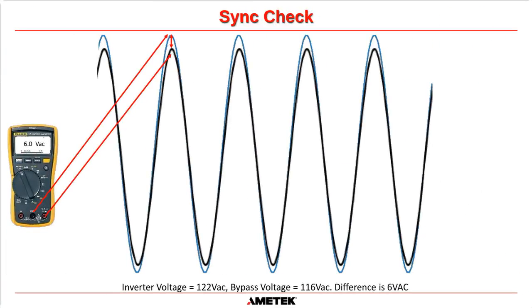And then also, not only phase displacement, you can see here that these waveforms are actually perfectly in phase. The difference in this one is that at the bottom and the top there is a voltage difference. The inverter voltage is higher than the bypass voltage. So let's say the inverter voltage is 122 volts, and the bypass voltage, which is dependent on power from your MCC, let's say in this system is 116 volts. That's a voltage difference of 6 volts AC. So even if these waveforms were absolutely perfectly in phase, with no electrical phase displacement whatsoever, you are still going to measure roughly a 6 volt difference, because of the change in voltage between the inverter and the bypass.